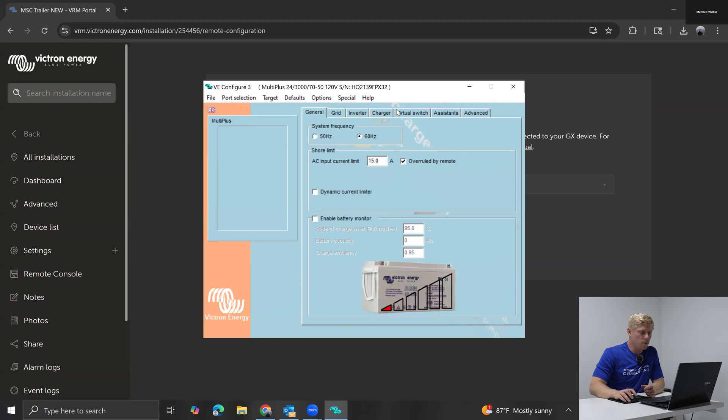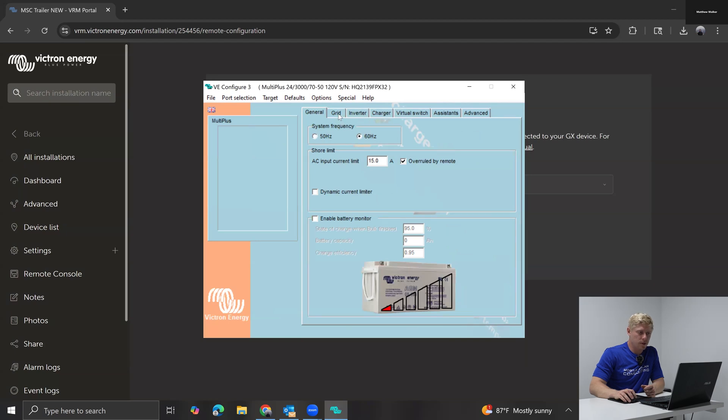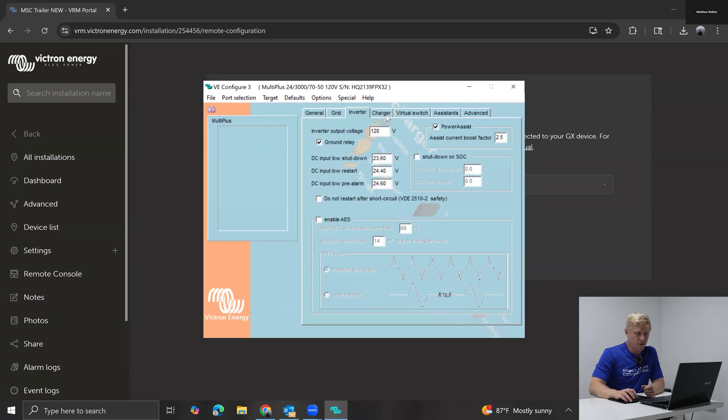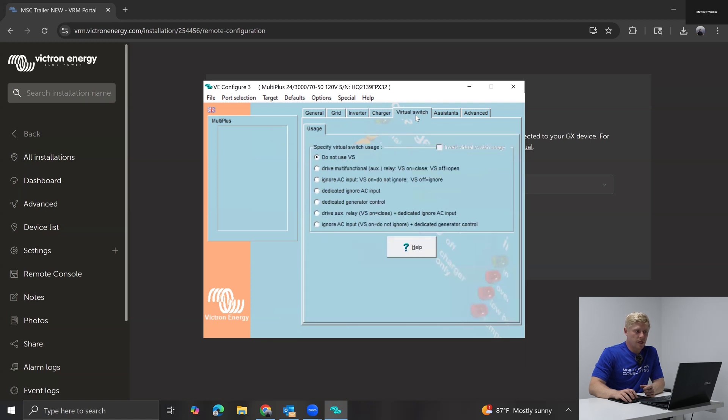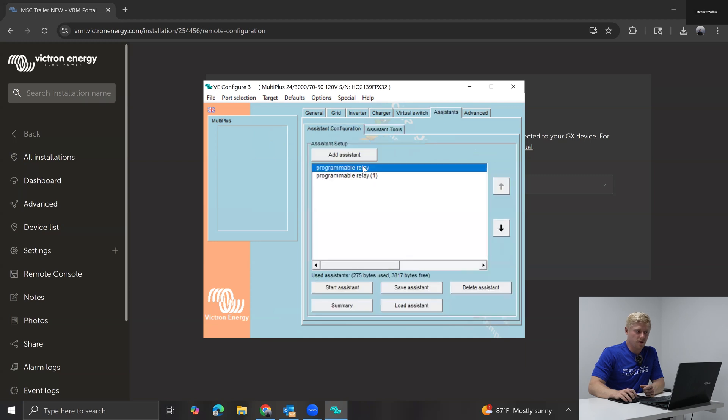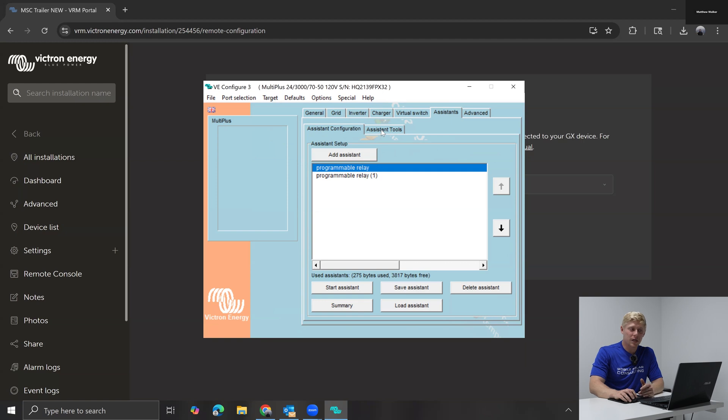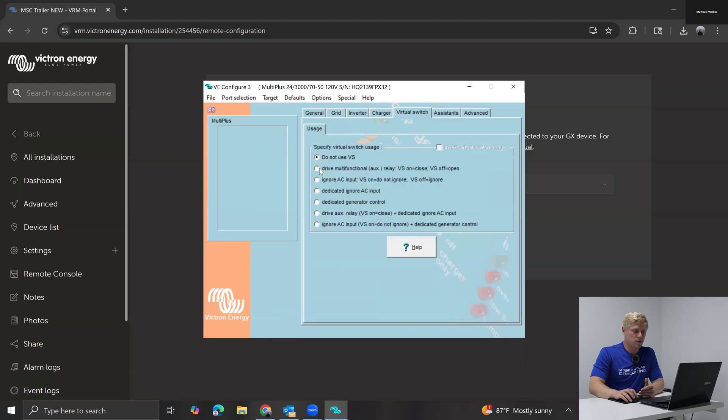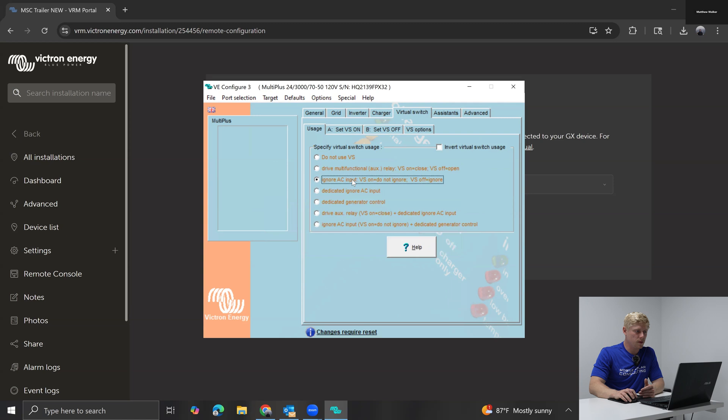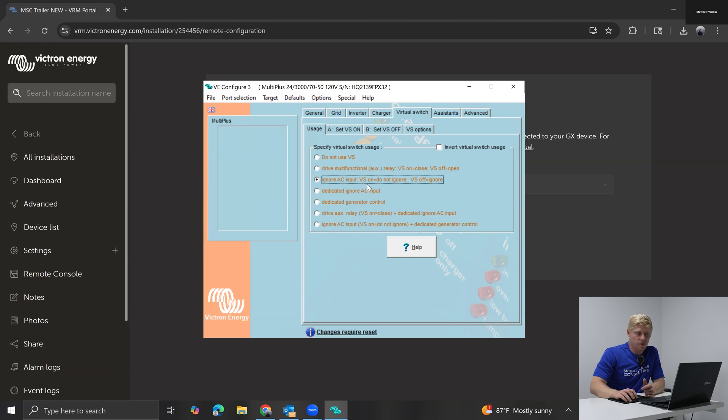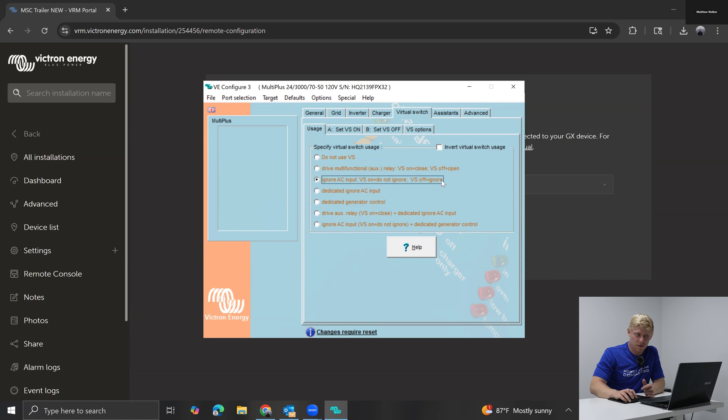And we'll be able to adjust any of the settings on the inverter. But today we're going to look at the virtual switch functions. So at the moment, if you're using any assistants like me, just know you're going to lose the assistant functionality when you turn on virtual switch because you cannot use both at the same time. So we're set up here to ignore AC input. This I find a little confusing. Virtual switch on means do not ignore. So virtual switch on means grid is on, virtual switch off means the grid is off. So we're going to stick with the way it is.